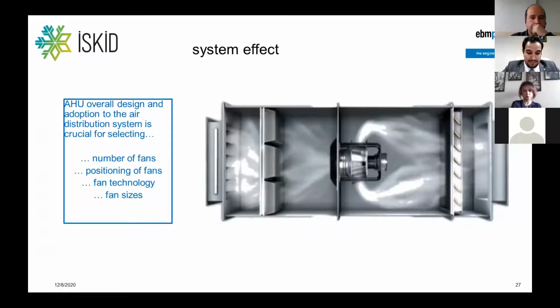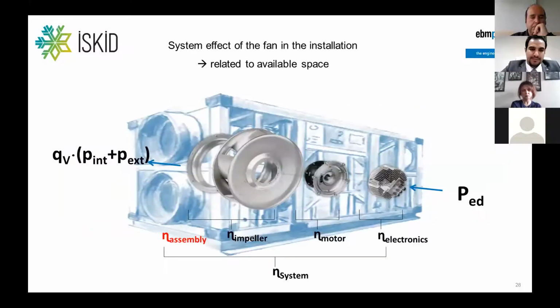So system effect, yes. Overall design and adaptation to the air distribution system is crucial for selection. It has an effect on the number of fans and how to position the fans, and also on the fan technology, and for sure on the fan sizes. So it cannot be said that this design or that design is the best one to be used in an air handling unit. We have to consider also the circumstances of the usage of the installation, if the airflow is going axial in and axial out, or if there's a bend, axial in and radial out. Could be, yeah, there are various ways of building AHUs, as you know.